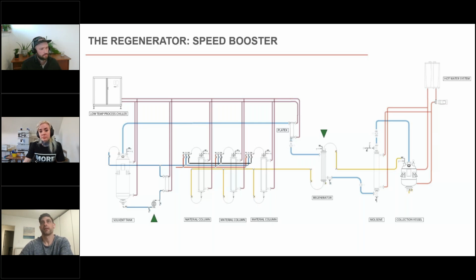Some of the other systems I've seen have that coil in coil heat exchanger on the way to the ice creator. And the surface area - let's compare the surface area of a coil in coil heat exchanger, it's like 20 versus 40x. You can get a lot of different sizes of plate exchangers, but that heat exchanger can be a great shortcut when you don't have the kilowatts or the gallons per minute of a giant pump on a big industrial chiller, because the amount of surface area that a plate exchanger can pack into a small container is incredible.